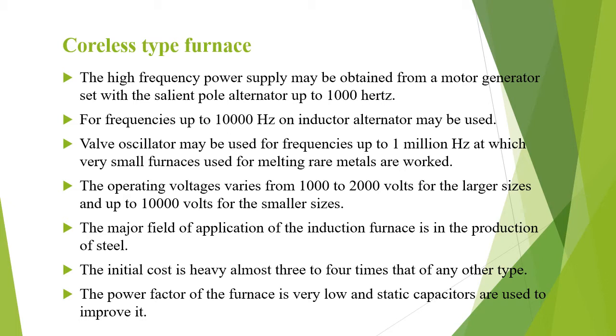The major field of application of the coreless type induction furnace is in the production of steel. It is used for the production of highest grade alloy steels since there is no contamination of the product by impurities. The initial cost is high, almost 3 to 4 times that of any other type of furnace, so it is economical for sizes up to 4 to 5 tons. The power factor of the furnace is very low, so static capacitors are used to improve the power factor.